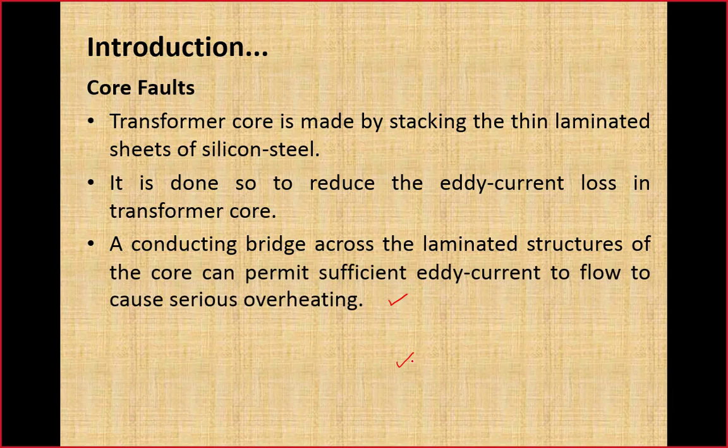Now let's see what type of problem may occur. A conducting bridge across this laminated structure of the core can permit sufficient eddy current to flow to cause serious overheating. This can happen due to damage to the lamination or insulation between those sheets, or due to breakdown of insulation of the nut bolts used to clamp these sheets together. That nut bolt is actually isolated from the lamination, but if that isolation gets damaged, the nut bolt can develop a bridge, or you can say a conducting path, among these laminations.